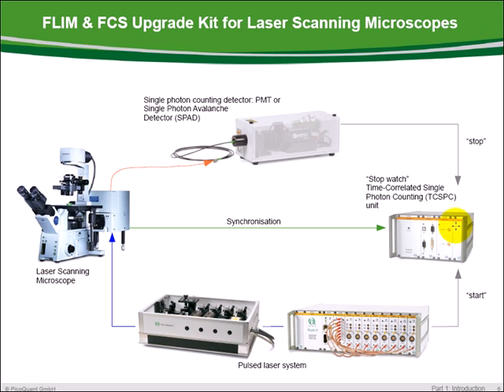This very fast stopwatch — a time-correlated single photon counting unit — measures the time between the laser pulse, coming from the laser driver, and the stop pulse, coming from the photon detection unit. In addition, a synchronization signal coming from the microscope allows reconstructing the FLIM images.